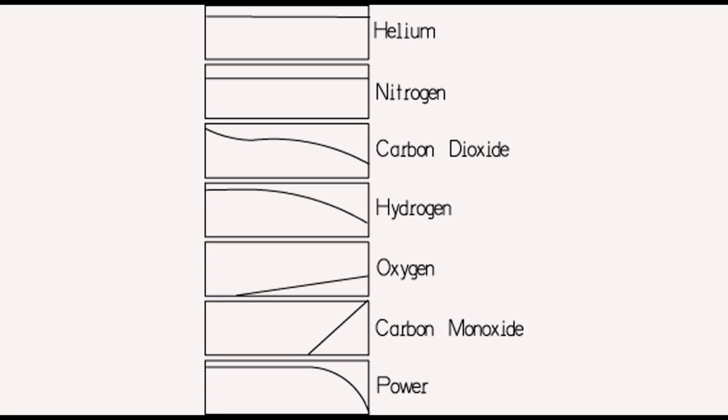There's no numbers on these pictures because you can make them fit whatever you want, so let's assume the power line across the bottom is a thousand hours long and the power up the side could be 50, 60, 80, 100 watts depending on your laser. The picture is likely to be the same no matter what your power. As we look up the stack of graphs, we'll see that probably around 65 to 70 percent life of your tube, the carbon monoxide starts to grow at a fairly rapid rate.